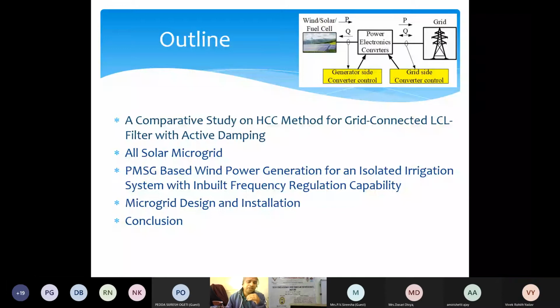Along with that, we will see the LCL filter design as well as active damping, which is very important today, because if there is resonance or chattering in the network, how will you integrate it to the grid? As soon as you integrate to the grid, the high frequency component will create electromagnetic interference, and it may produce a large amount of distorted waveform in the control circuit.